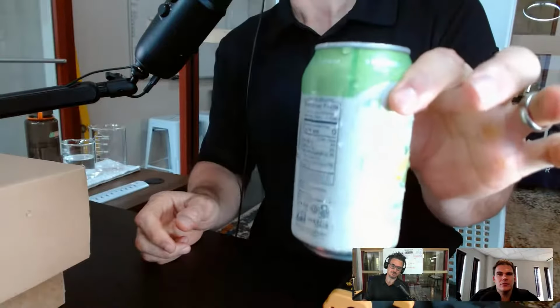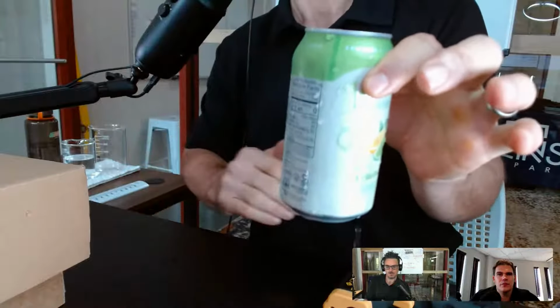Okay, so 43 degrees. It's a little wet because it came out of the cooler, but this will sweat in this space because the dew point's 54. The point here is anything colder than the dew point is going to cause condensation, which is why we make cooling coils colder than the dew point of the air. That's how we remove humidity. That's the only way we remove humidity with a cooling coil.